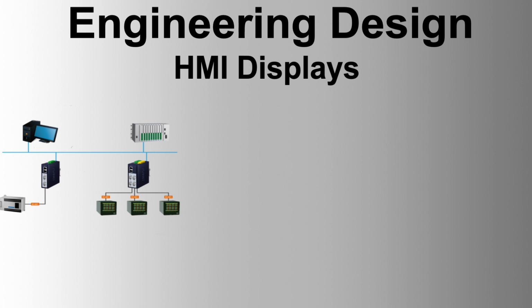Used by technologists, operations management, and engineering for checking plant operability, parameter modification, process control, diagnosis, condition monitoring, and system maintenance. The main console HMI should include a hardwired switch panel with individually labeled and logically arranged ESD switches, depressuring switches, and MOS enable switches. Operational override switches should be avoided by using automatic timer functions in the IPS.